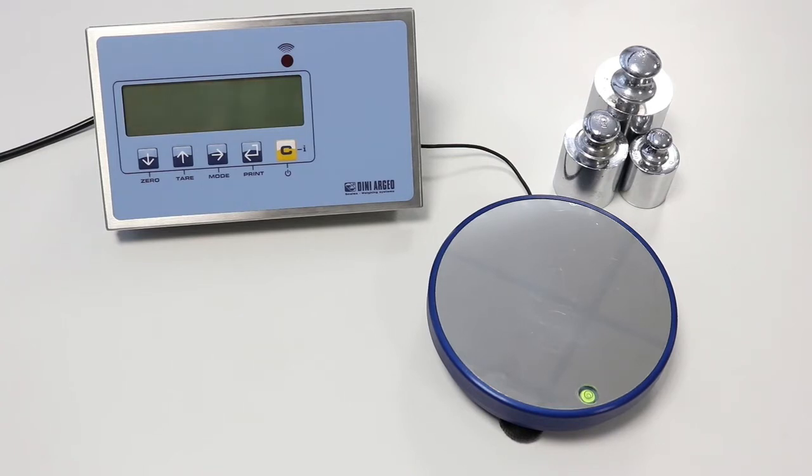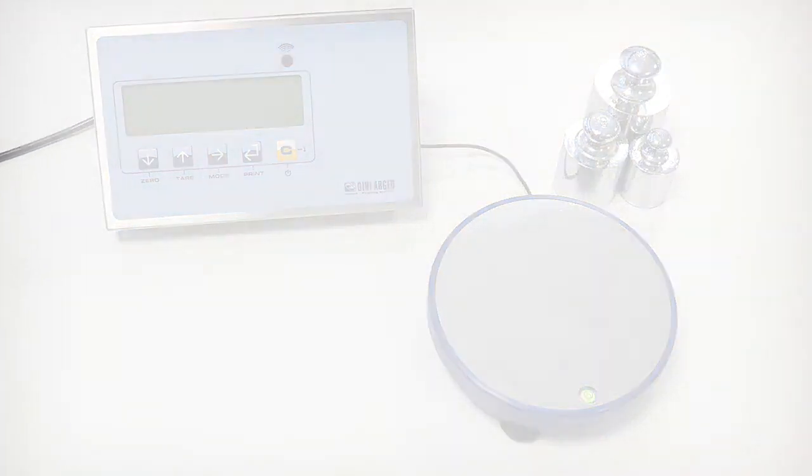Before starting the programming, in order to obtain the best performances, we suggest to correctly set the scale level. On all Dini Argeo scales, you have the bubble to do it easily. Another suggestion, especially for weighing systems with many load cells, is to check the signal input before starting using the diagnostic menu.